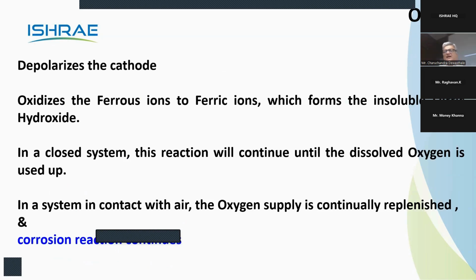Now, what is the process of oxygen? It depolarizes the cathode, meaning it defunctions the cathode, so it oxidizes ferrous to ferric, which forms insoluble ferric hydroxide. In closed loop circuits, this will go on continuing as long as oxygen is present. But in open loops, like a hot and cold circuit, oxygen ingress occurs and the corrosion reaction continues. So oxygen needs to be taken care of in the system.